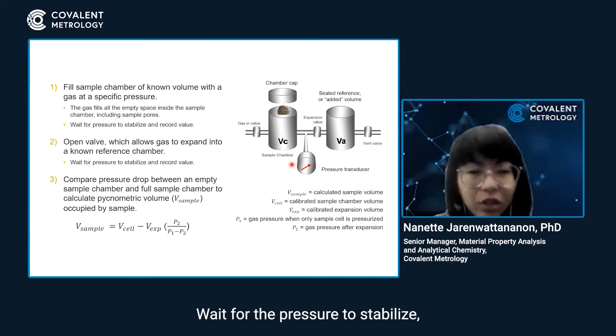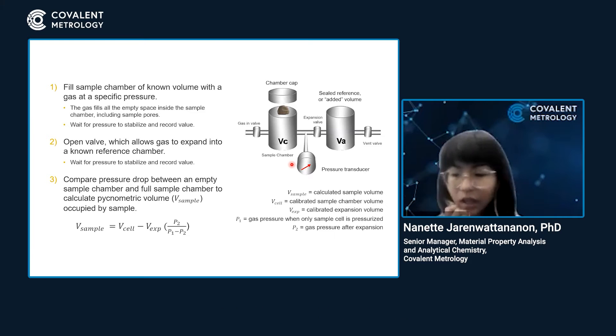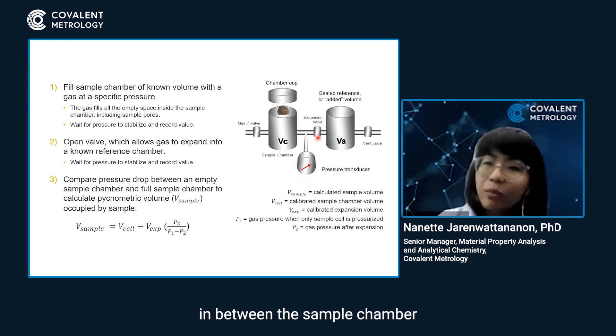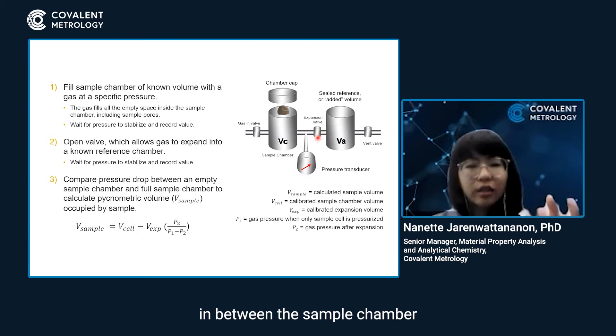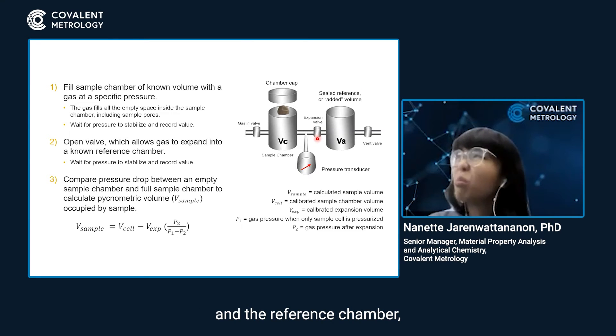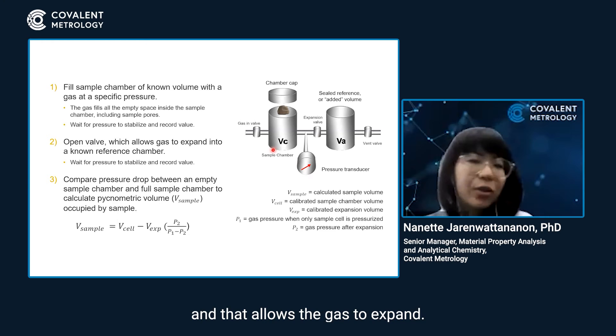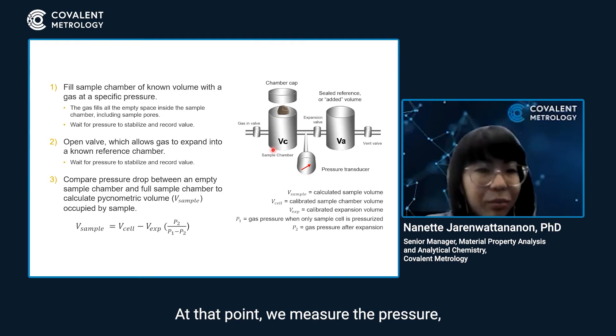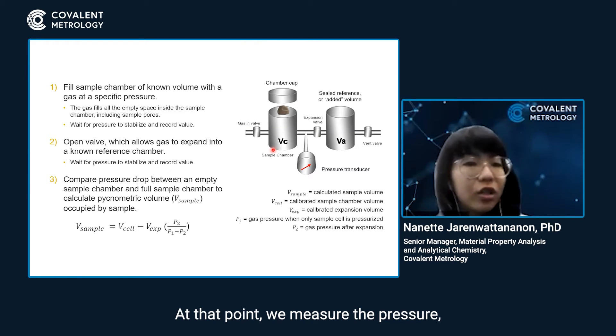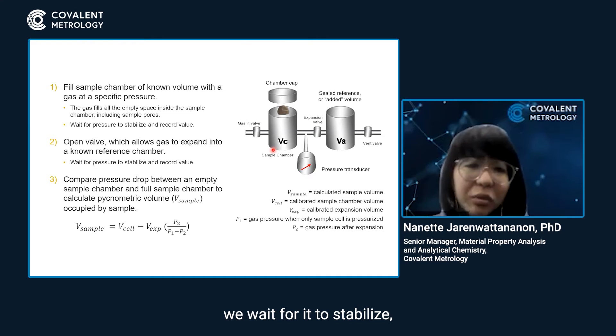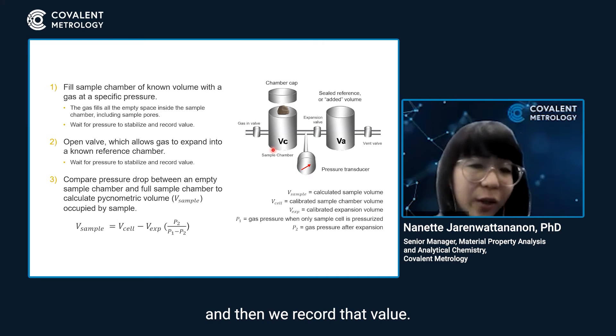We wait for the pressure to stabilize and record that value. Then we open up a valve between the sample chamber and the reference chamber, allowing the gas to expand. At that point, we measure the pressure, wait for it to stabilize, and record that value.